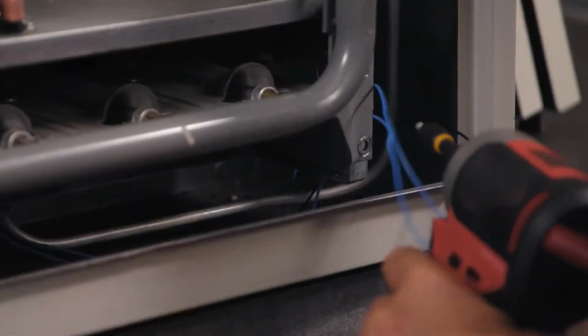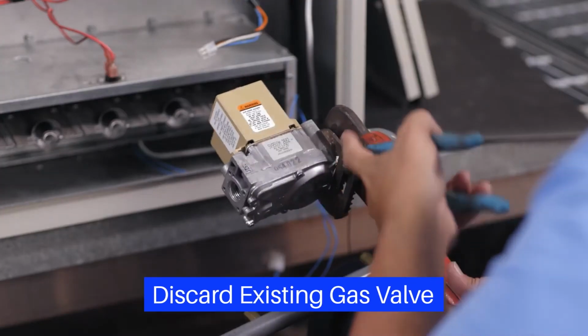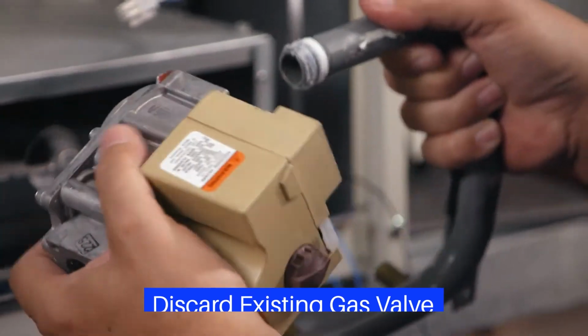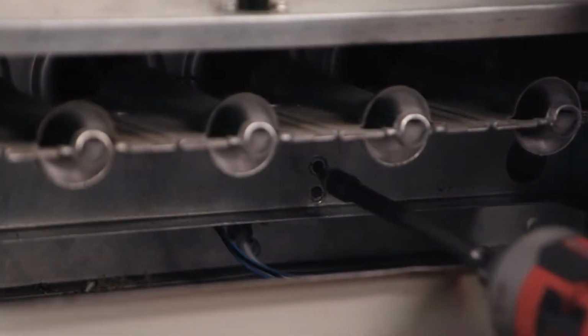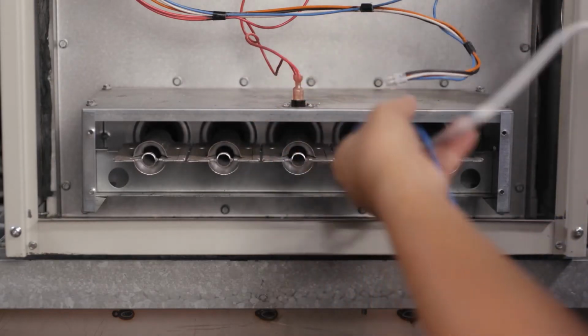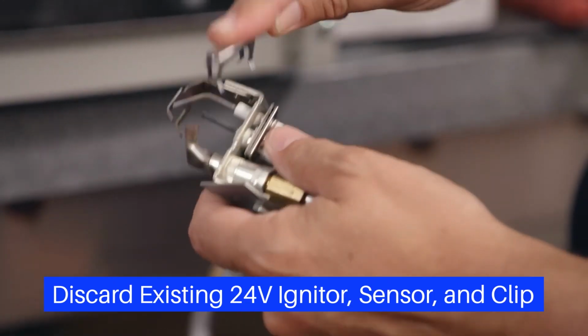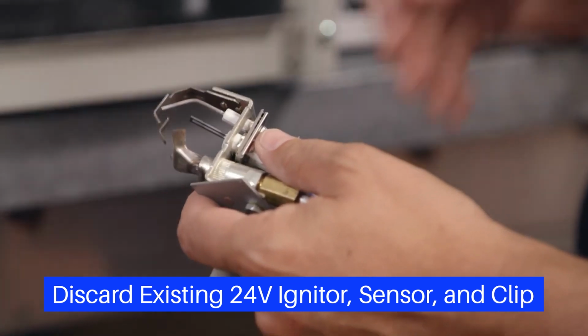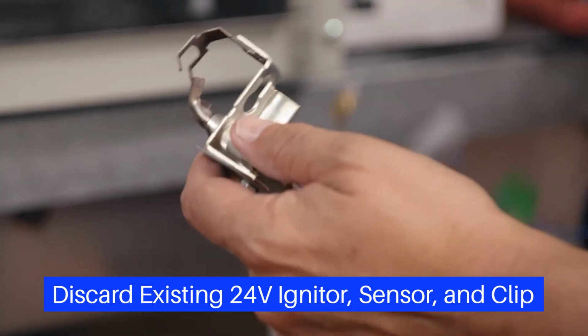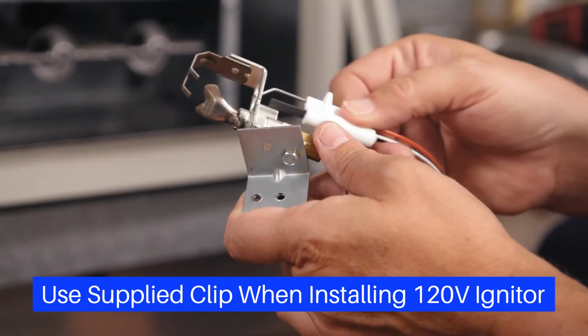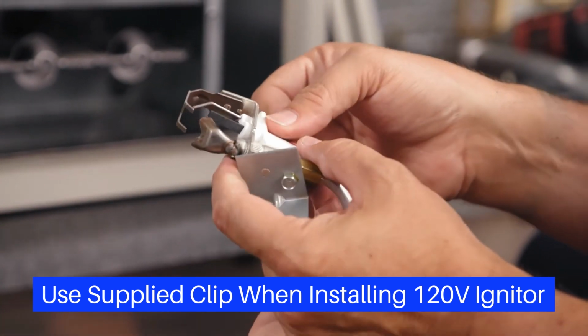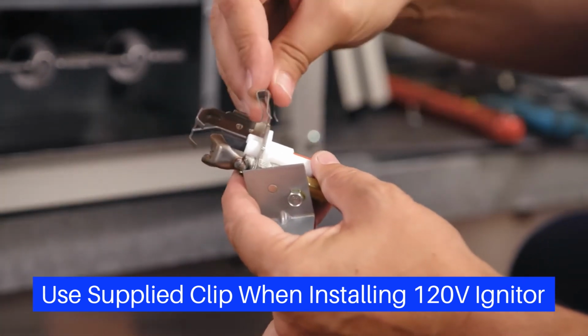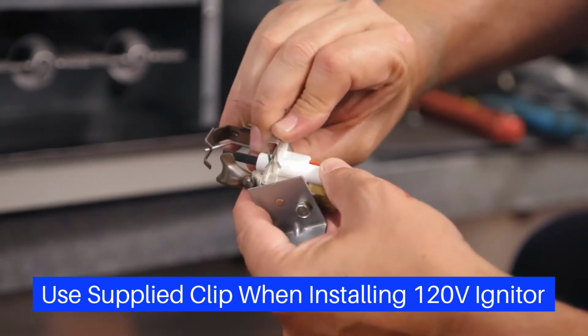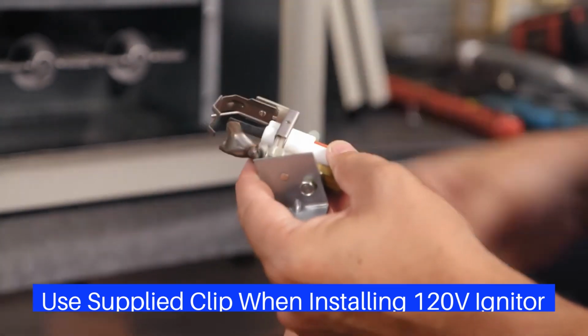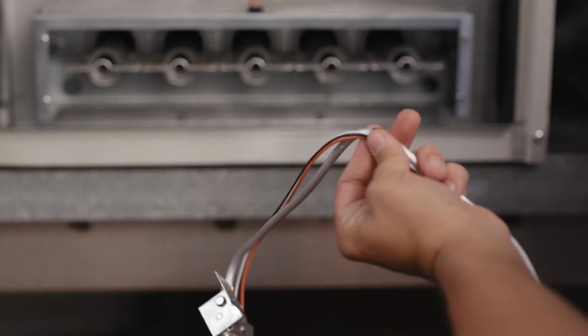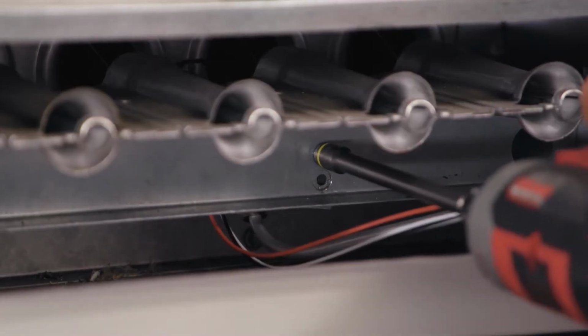If necessary, disconnect the gas manifold to unthread the valve. Remove the pilot assembly. Unclip the 24-volt hot surface igniter flame sensor assembly and remove it from the pilot assembly. Install the 120-volt hot surface igniter flame sensor assembly connected with the 3-pin extension harness on the pilot assembly. Secure with the supplied new clip. Reinstall the pilot assembly.